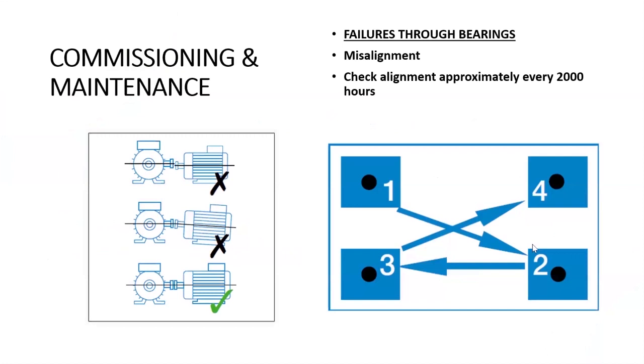Misalignment has been found to cause a lot of motor bearing failure. The rule of thumb is that after every 2,000 running hours, ensure you do your alignment check and you proceed on. You do not wait till you observe any misalignment. Every 3 months, you do your alignment. In so doing, you help your motor bearings to run successfully, and you avoid unnecessary breakdown. Don't wait till you have an issue. Have a strategy to check your alignment, and your bearings will last, and your motors will also last.